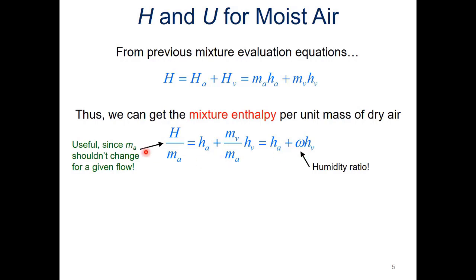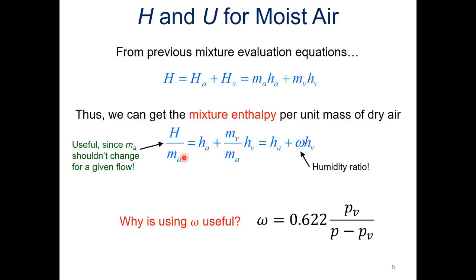Why is using omega useful? Because we have an equation to calculate it using the partial pressure of the vapor — which we can usually find without much difficulty — and the total mixture pressure, which we usually have information on. Also, the mass of dry air remains constant through the processes we'll be looking at. For example, if moist air travels through a cool duct and we cool below the dew point, things condense — but none of the dry air condenses. The dry air continues along; it's only the vapor that condenses.